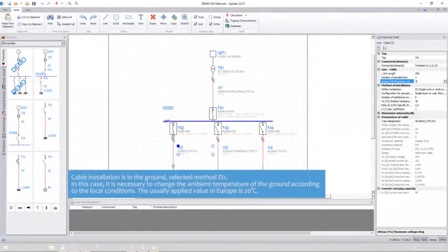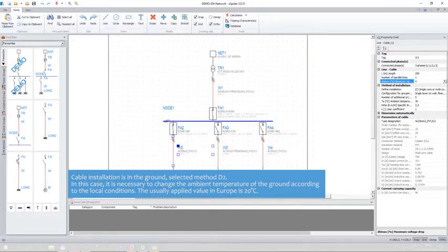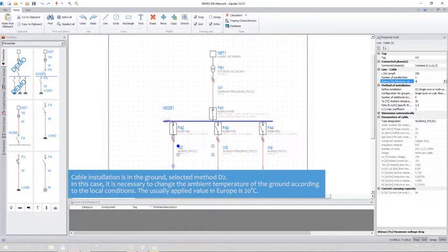The cable is installed in the ground. The selected method is D2. In this case, it is necessary to change the ambient temperature of the ground according to the local conditions. The usually applied value in Europe is 20 degrees centigrade.